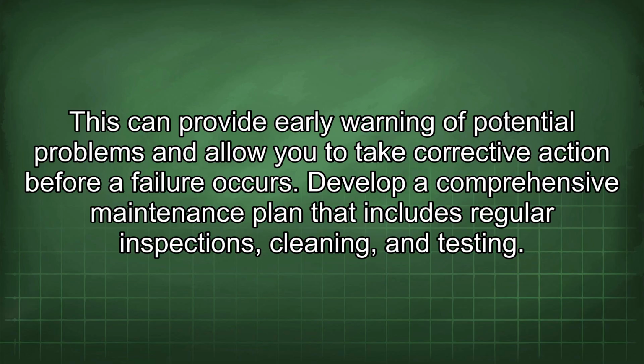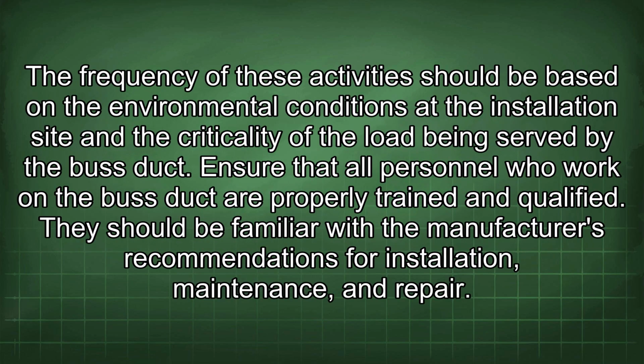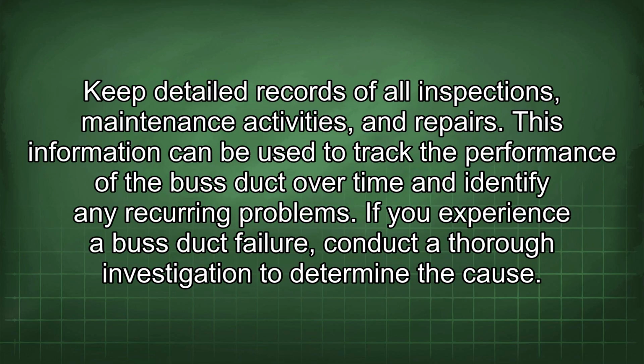Develop a comprehensive maintenance plan that includes regular inspections, cleaning, and testing. The frequency of these activities should be based on the environmental conditions at the installation site and the criticality of the load being served by the bus duct. Ensure that all personnel who work on the bus duct are properly trained and qualified. They should be familiar with the manufacturer's recommendations for installation, maintenance, and repair. Keep detailed records of all inspections, maintenance activities, and repairs. This information can be used to track the performance of the bus duct over time and identify any recurring problems.